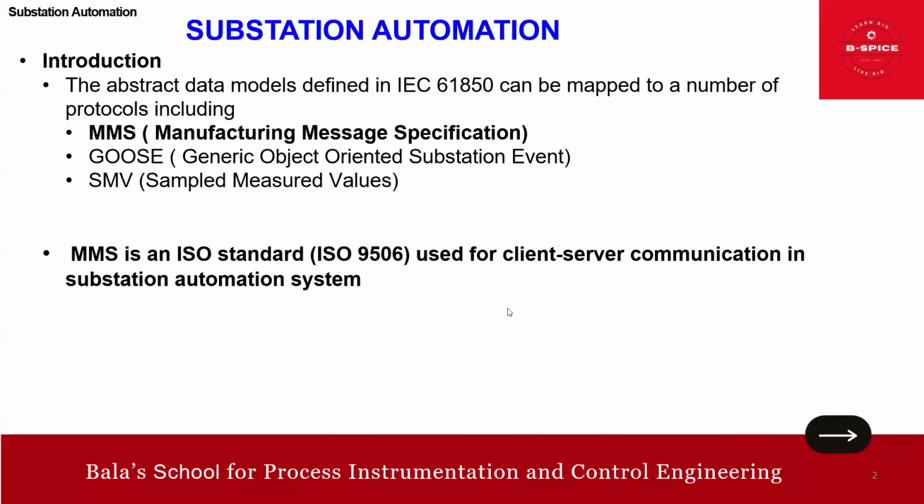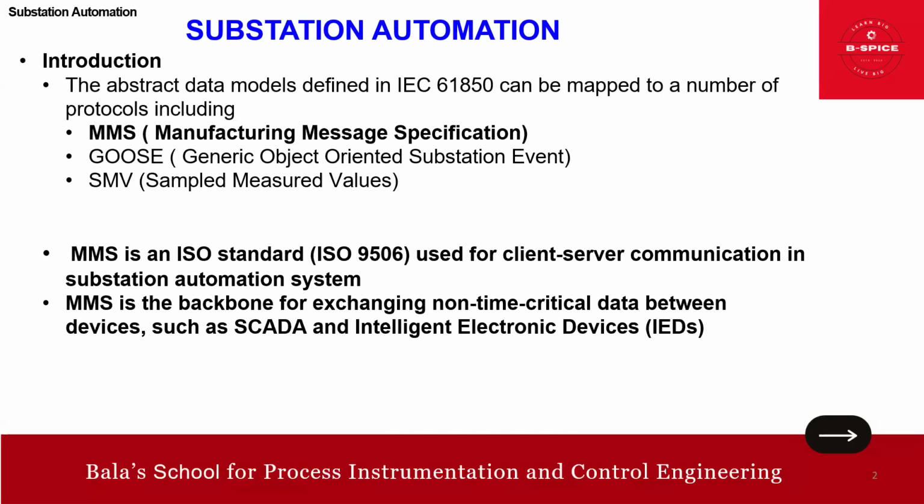Now in this session, we'll focus on MMS. What is MMS? MMS is an ISO standard 9506 used for client server communication in substation automation systems. MMS is basically the backbone for exchanging non-time critical data. Just note this, friends: exchanging non-time critical data between devices such as SCADA and intelligent electronic devices, that is IEDs. Just remember that.